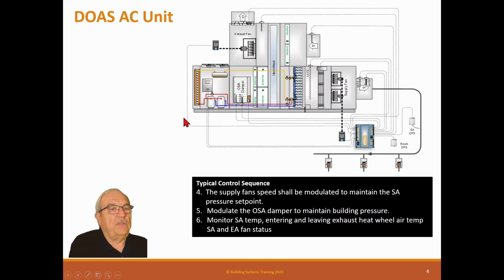The supply fan speed should be modulated to maintain supply air pressure set point, just like any other VAV system. Modulate the outside air damper to maintain the building pressure. Monitor supply air temp, entering and leaving exhaust heat wheel air temp, and supply air and exhaust air fan status. So remember, these systems out here might be VAV or they might not. They might be constant volume, but it doesn't make any difference, because this outside air conditioning is providing a constant flow of air into the space. But as these dampers might change for whatever reason, we can do VAV.